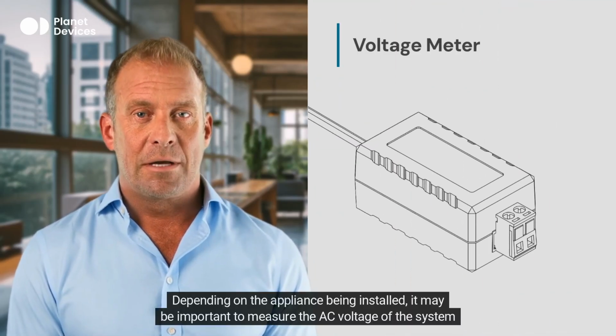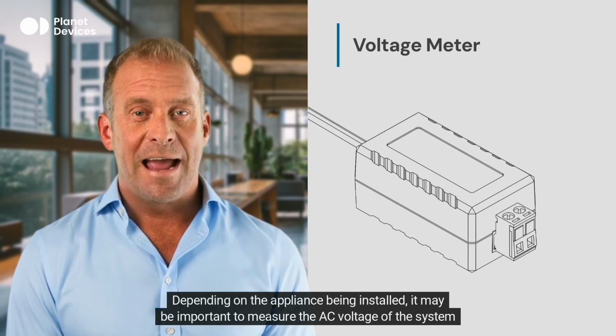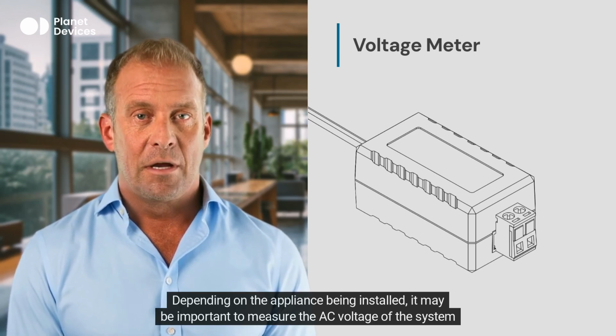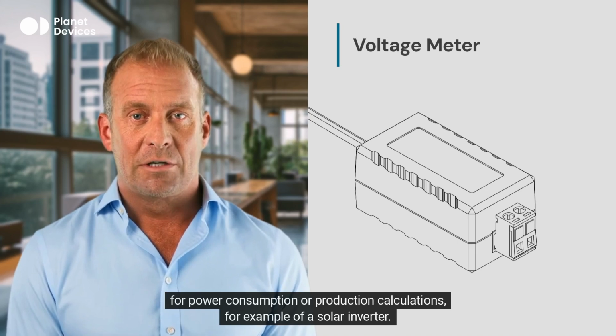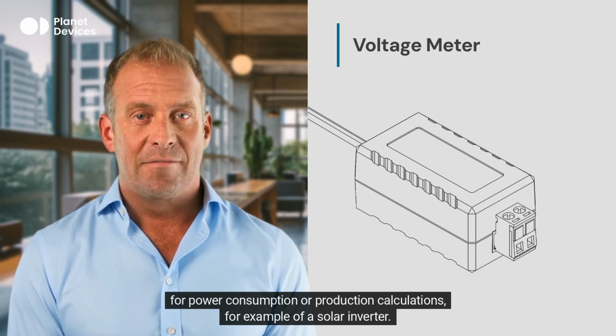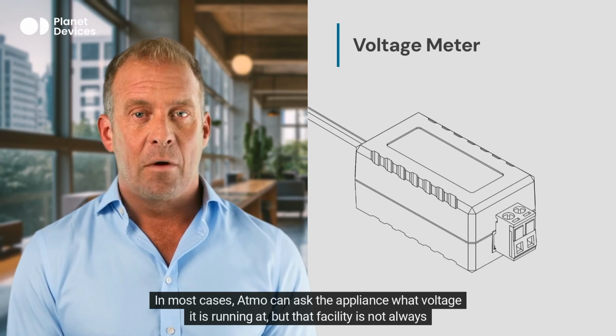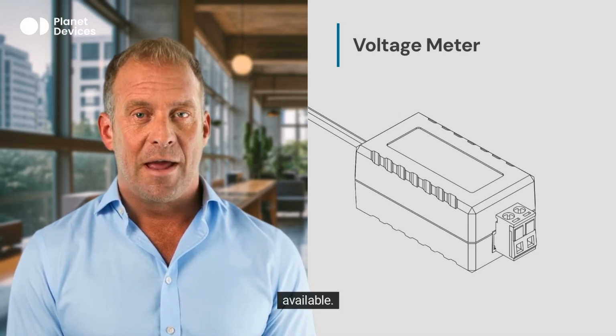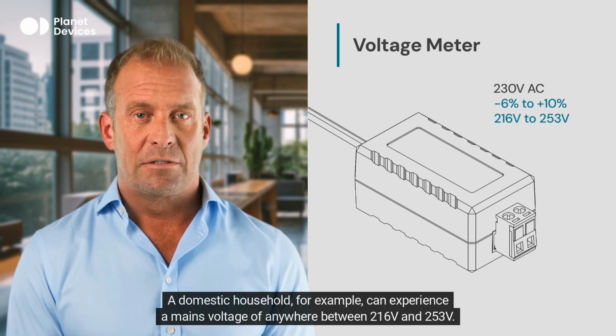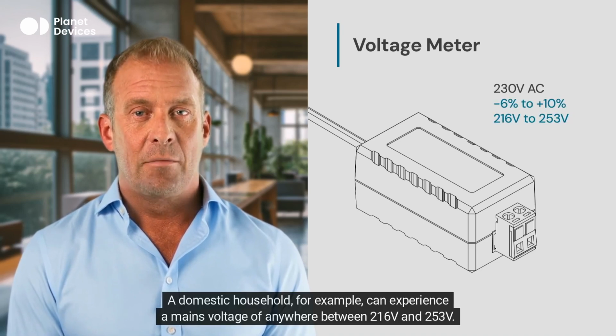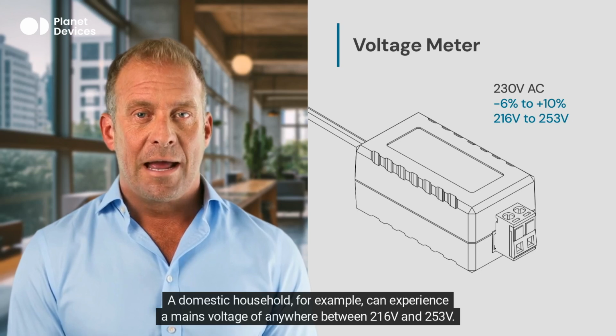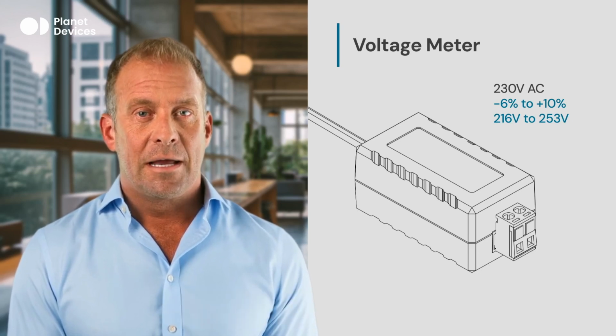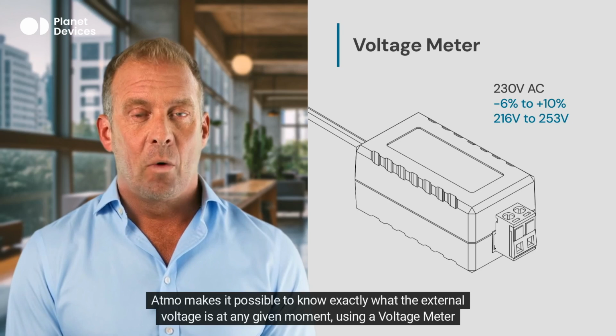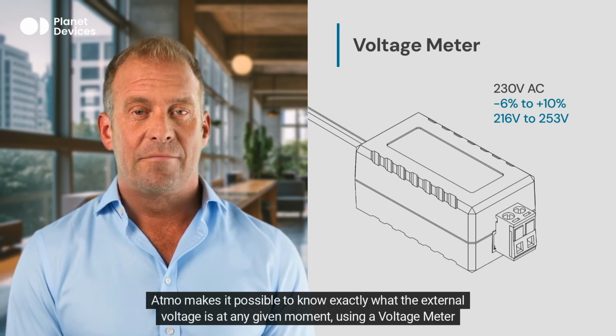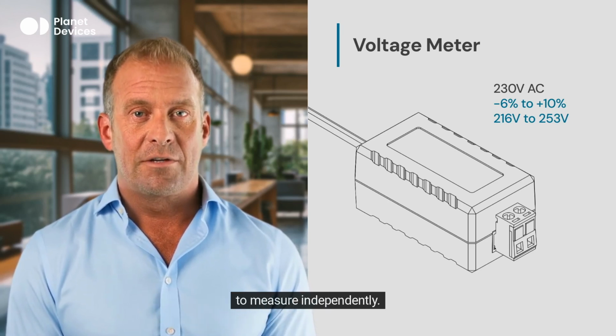Depending on the appliance being installed, it may be important to measure the AC voltage of the system for power consumption or production calculations, for example of a solar inverter. In most cases, Atmo can ask the appliance what voltage it is running at, but that facility is not always available. A domestic household, for example, can experience a mains voltage of anywhere between 216 volts and 253 volts. Atmo makes it possible to know exactly what the external voltage is at any given moment, using a voltage meter to measure independently.